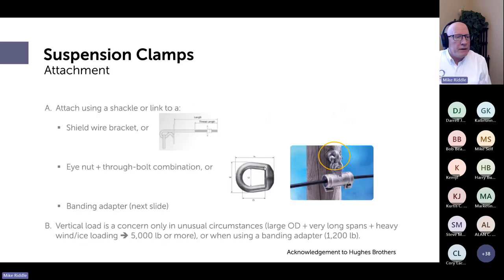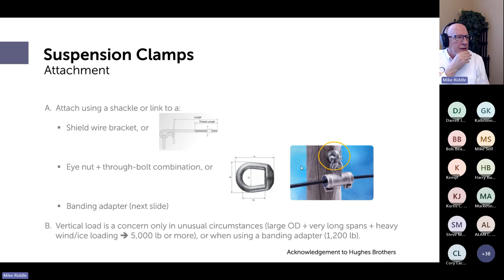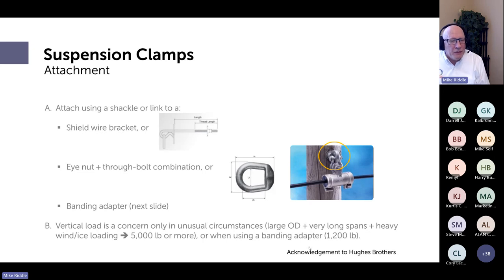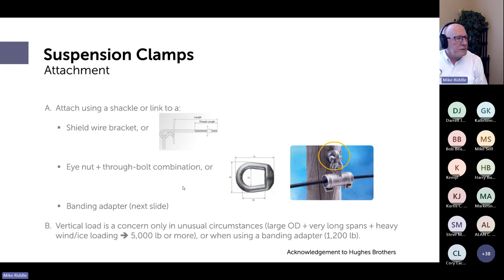I prefer the plain suspension — it's simpler, less expensive, and easier to install. But the AGS-style is excellent too. For attachment at the pole: supports use a through bolt or banding adapter; suspension clamps can use a shield wire bracket, a through bolt with eye nut, or a banding adapter. Vertical load is rarely a concern with ADSS suspensions — it would need to exceed 5,000 pounds, which is very hard to achieve with ADSS cable.